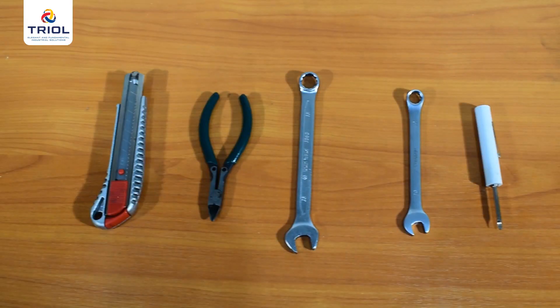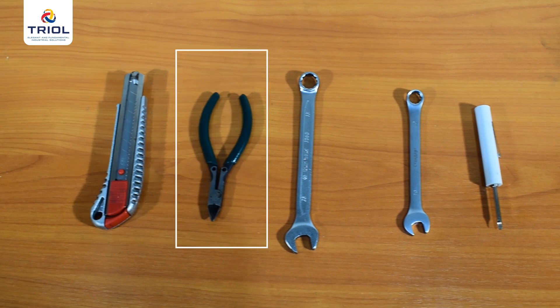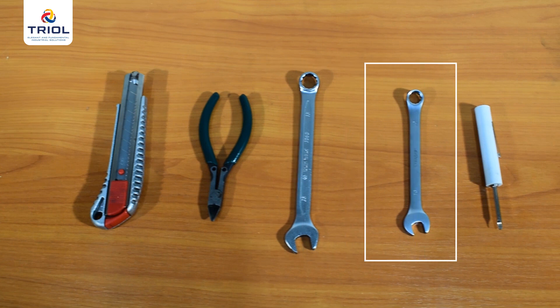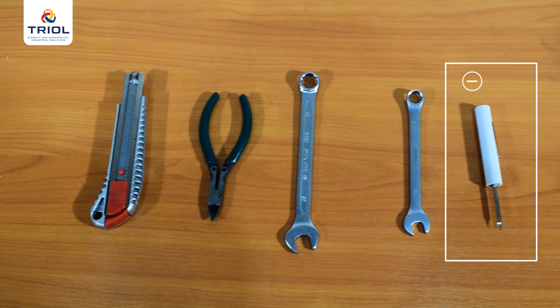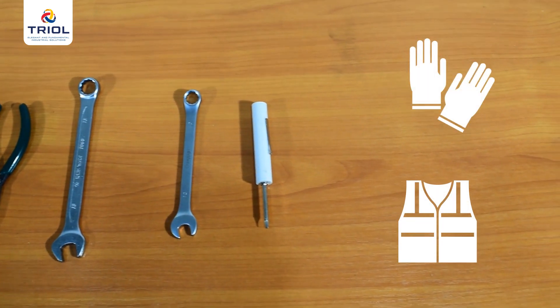To install and unpack the high voltage choke, you will need a stationery knife, side cutters, a 13mm spanner for mounting brackets to the high voltage choke (either open-end or other suitable), a 10mm spanner for mounting the earth wire, a slotted screwdriver for installing and clamping the wire in the terminal, and a Phillips screwdriver for installing the brackets on the surface card. We recommend using special clothing and protective gloves when unpacking.